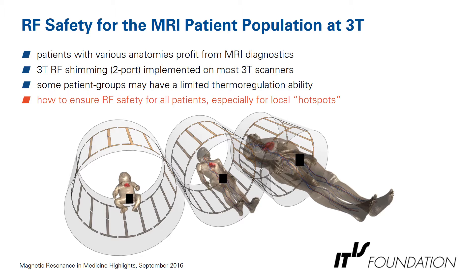Some background for the study: RF safety for the MRI patient population at 3 Tesla. We have patients with very differing anatomies that profit from MR diagnostics — from a baby up to an adult obese model or patient. At 3 Tesla, we have RF shimming or two-port RF shimming implemented on most scanners. Additionally, some patient groups may have limited thermoregulation ability. The question is how to ensure RF safety for all patients, especially for local hotspots.